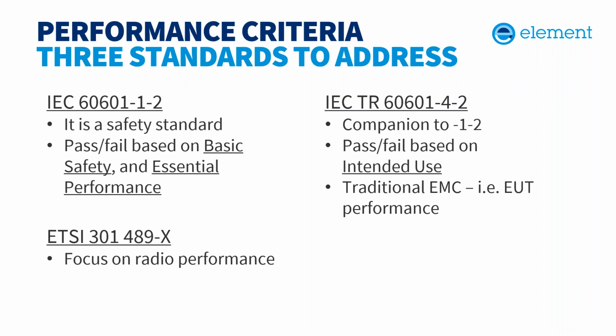If a medical device does not have any functions which are deemed to be essential, then -4, -2 might be more appropriate for some of them. And then -4, -2, as we said, is about the usability of the device, not essential performance. So if a device doesn't have patient critical items identified under essential performance, you still need to think about monitoring them during testing. And then 301489-X addresses radio performance.